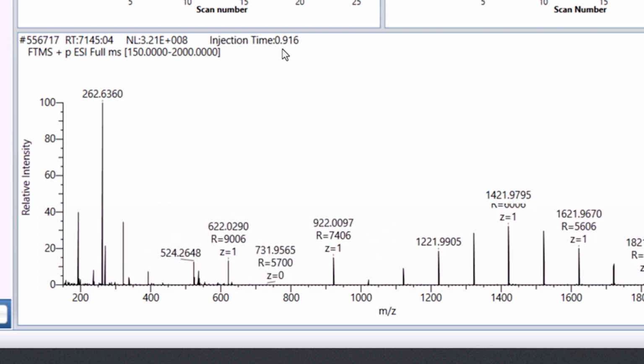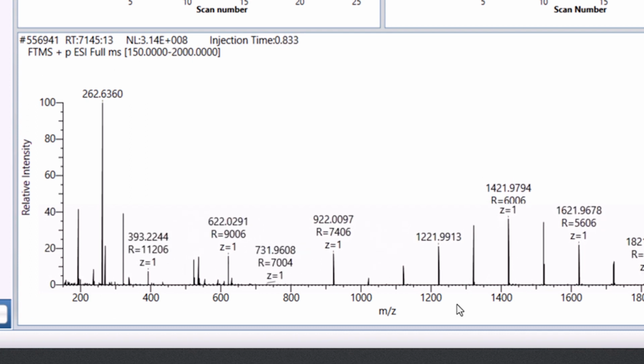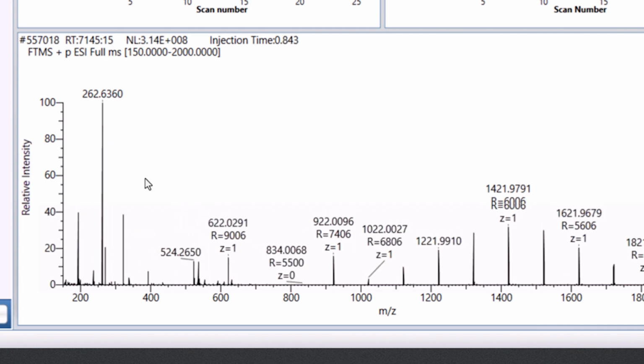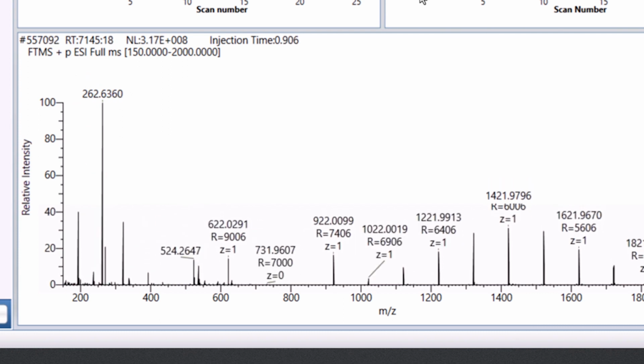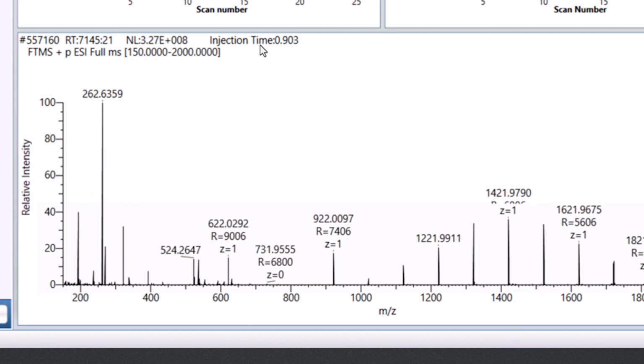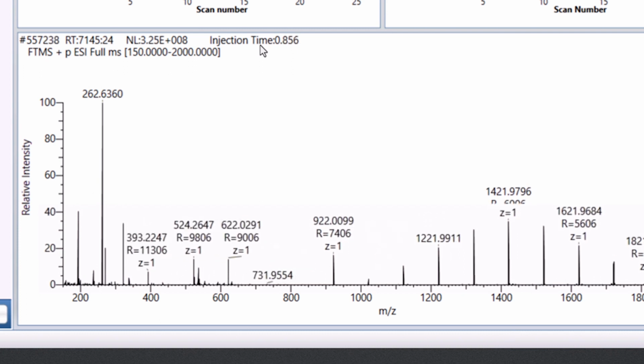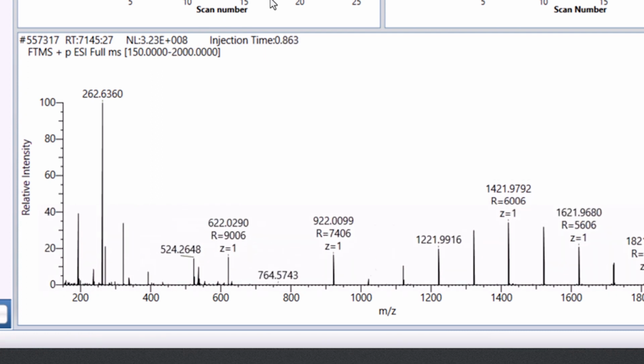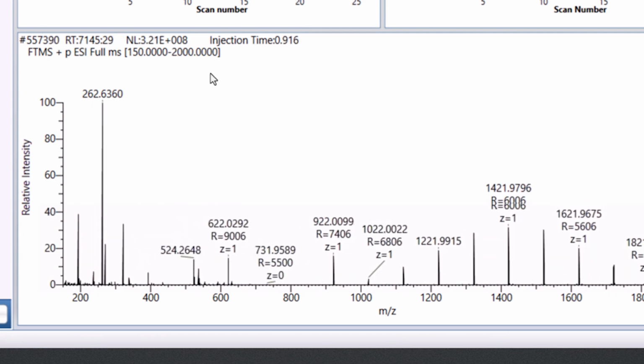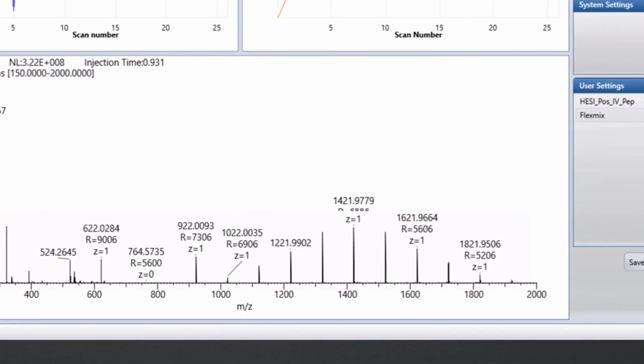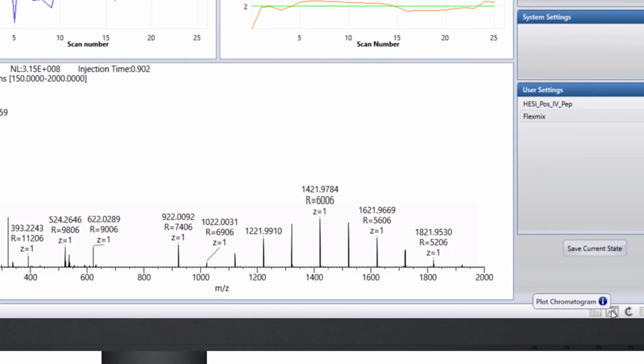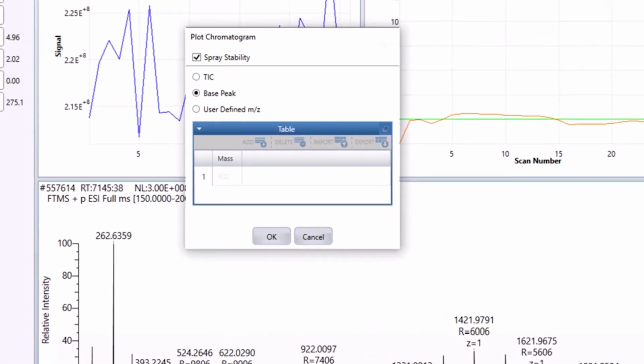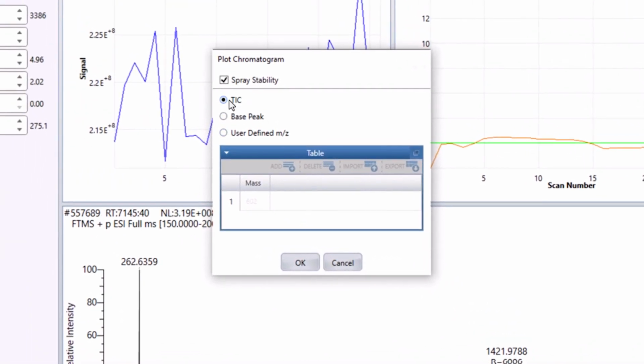So maybe it's dirty. So you want to make sure, be diligent about this, always have an injection time below 1 millisecond. And then over here, you can see the top intensity peak is 3E8, and that's a good reference range. And if you have questions about what the view of the TIC should look like for flex mix, the flex mix solution has guidelines in the PDF that comes with the product or on their website. So I would encourage you to check that out. But now that we're happy with our infusion here, less than 1 millisecond, I'm going to go ahead and do some real-time monitoring. So if I click on this lower right-hand button here, I'm going to do plot chromatogram, and I'm going to go ahead and monitor the TIC for spray stability. Click OK.